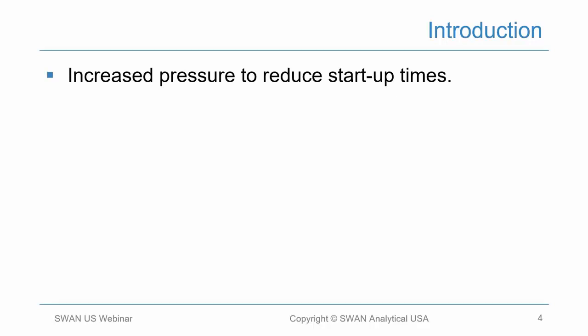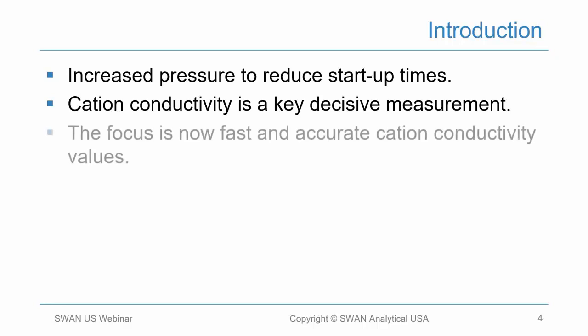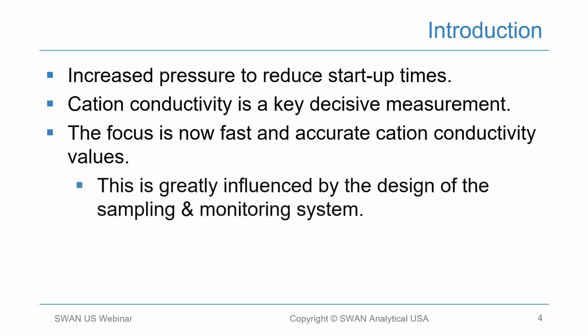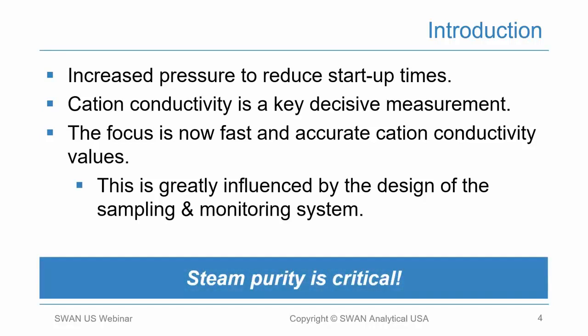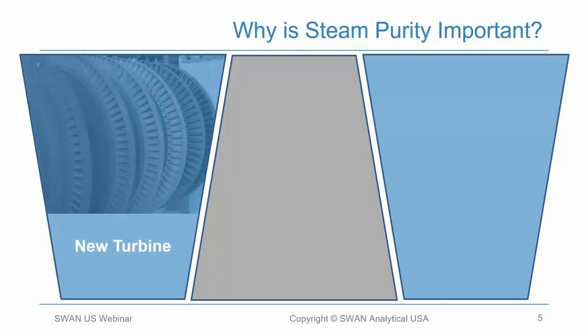In today's power generation environment, with all the renewables, there is tremendous pressure to reduce startup times on our traditional units as well as combined cycles. Cation conductivity is a key decisive measurement parameter for steam purity as well as condensate and feedwater. The focus today is on providing fast, accurate cation conductivity values to facilitate fast startups. The key message is: steam purity is critical to protect the assets.